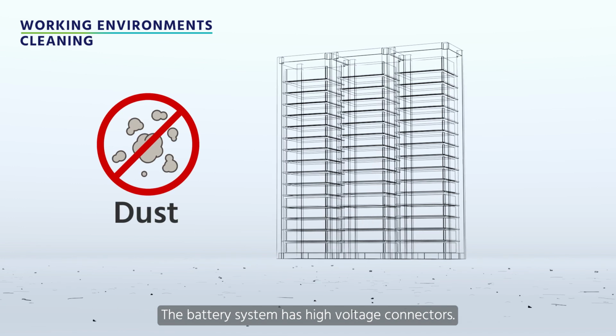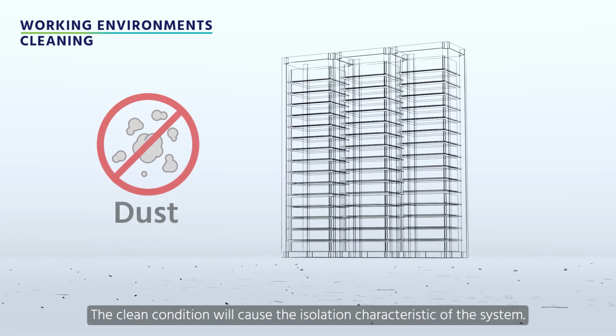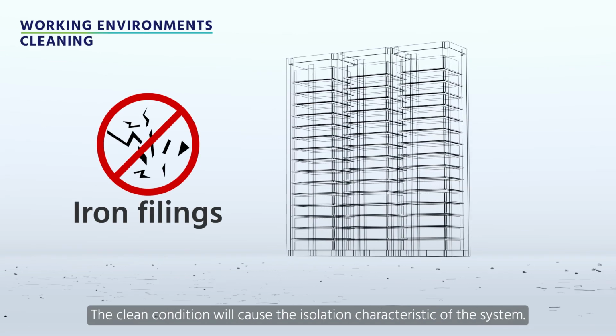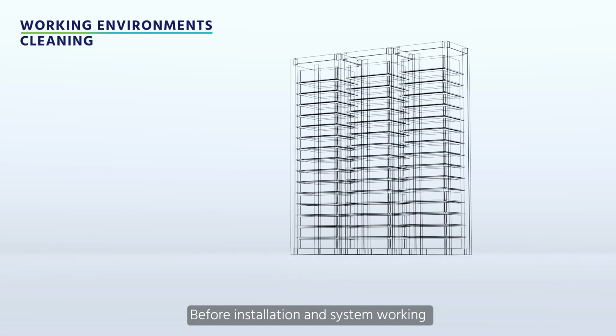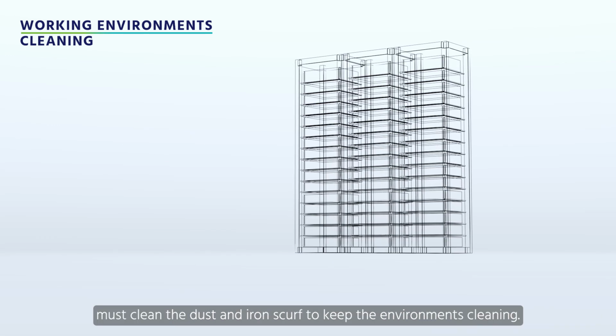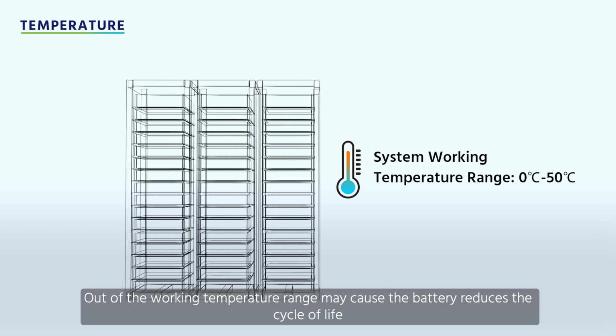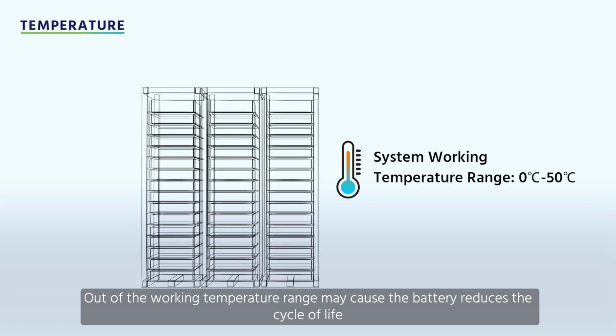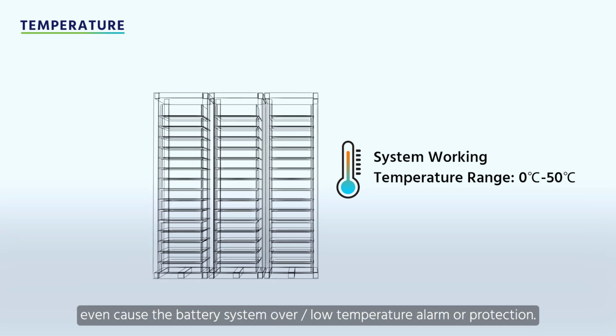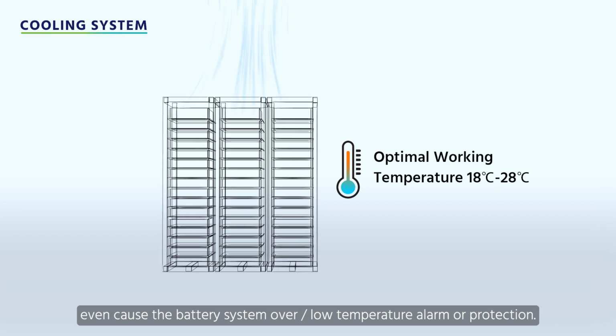The battery system has high voltage connectors. The clean condition will cause the isolation characteristic of the system. Before installation and system working, you must clean the dust and iron scurf to keep the environment clean. Out of the working temperature range may cause the battery to reduce its cycle life, and even cause the battery system over low temperature alarm or protection.